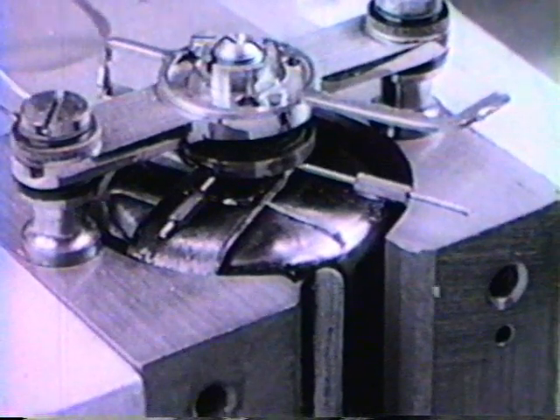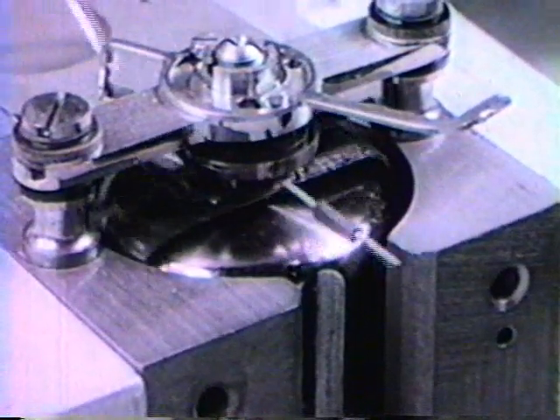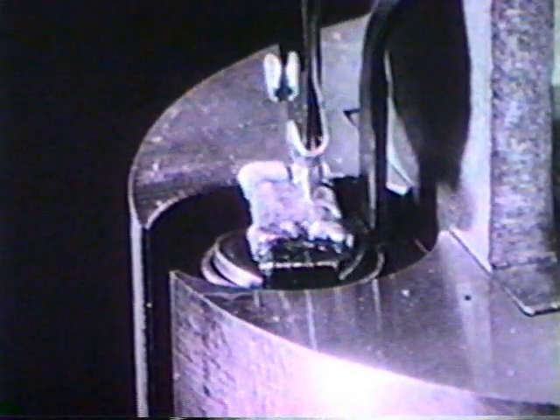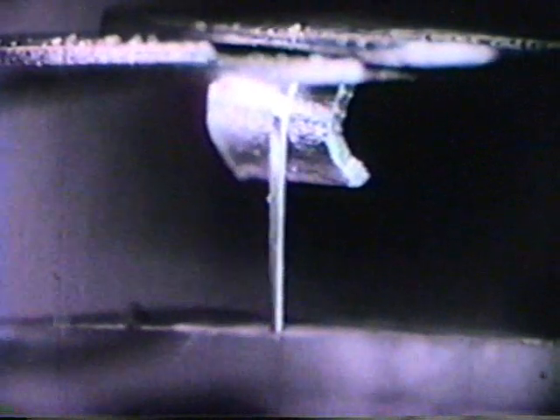The magnetic field surrounding the movable coil is controlled by the shape of the magnet and the cylindrical core. The way the moving coil is supported and restrained also affects the performance. Fiber, taut band, and jewel bearings are common supports. The magnetic field and the restraining mechanism are usually designed so that the deflection of the pointer is directly proportional to the coil current.